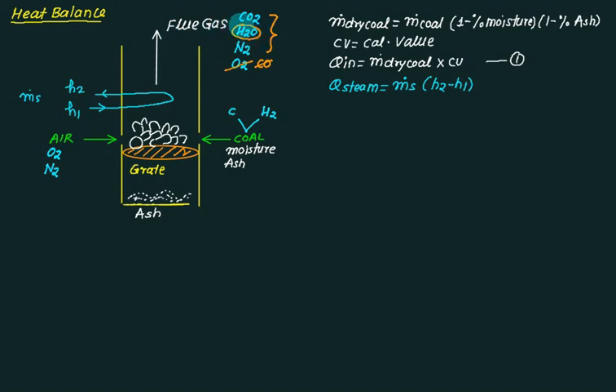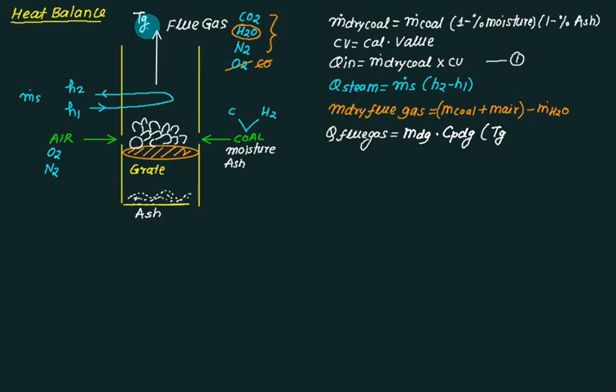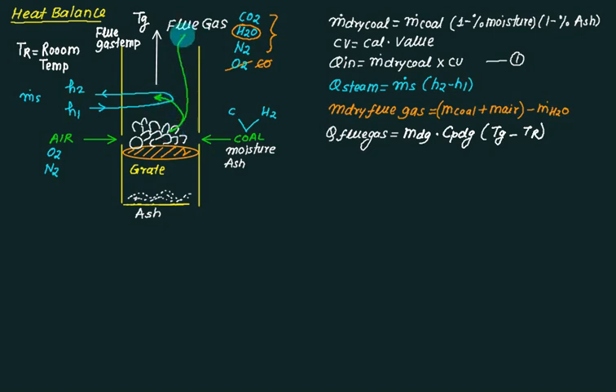All these constituents are called flue gas. If you subtract the mass of water vapor from flue gas, it is called dry flue gas. Heat carried by dry flue gas equals mass of dry flue gas multiplied by Cp of dry gas multiplied by (Tg minus Tr), where Tg is the flue gas temperature and Tr is the room temperature.